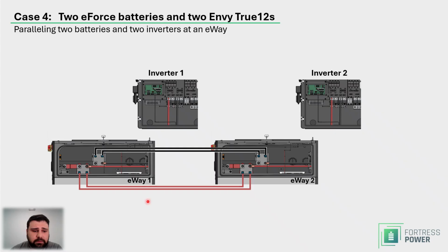I disagree, because with 1 positive and 1 negative, how big of a cable would you use? 4-aught? Okay, fine. Well, what can it do? On the best day, 300 amps? Well, the inverters can output 500 amps. Those cables would melt. So that's why you're using a bigger cable, because you want to make sure that if something happens and eWay 1 disconnects and stops accepting power, yet inverter 1 and inverter 2 are outputting maximum power, these cables can withstand the hit. And the bus bars have no problem with that, because the bus bars are rated at 750 amps. So that's why you have 2 pairs of cables, so that you have the ampacity that you need.